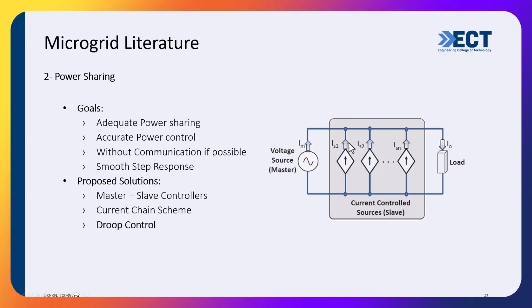Droop control is a control that drops the frequency based on the power we want to inject. The frequency of this bus is 50 Hertz. But if I make that inverter reduce the frequency a little bit, it will push more power to the grid. And by controlling the frequency reduction, or droop, you control how much power you are injecting to the grid. And this will give us accurate and adequate power sharing.